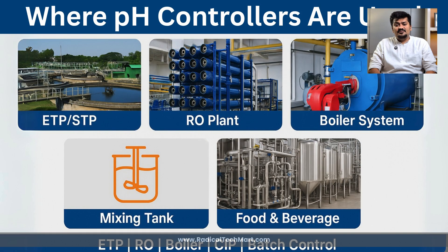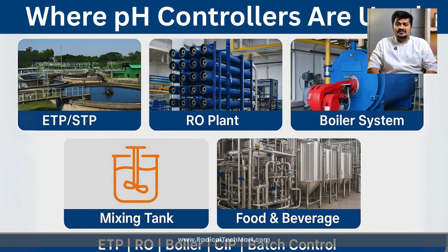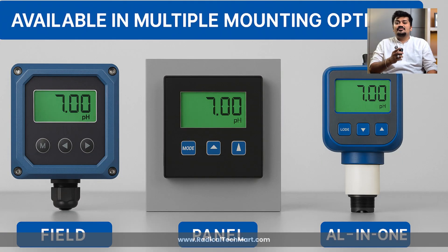Now let's cover where it's used. You will commonly find pH controllers in: first, ETP or STP plants for automatic acid or alkaline dosing; second, RO systems to protect membranes from extreme pH; third, boilers and cooling towers to maintain pH for corrosion control; fourth, chemical mixing tanks for batch process monitoring; and fifth, the food and beverage industry for CIP and fermentation pH control. They can be panel mounted, field mounted or even built into an all-in-one sensor unit.